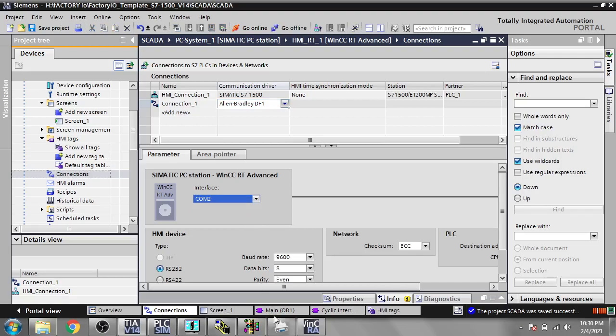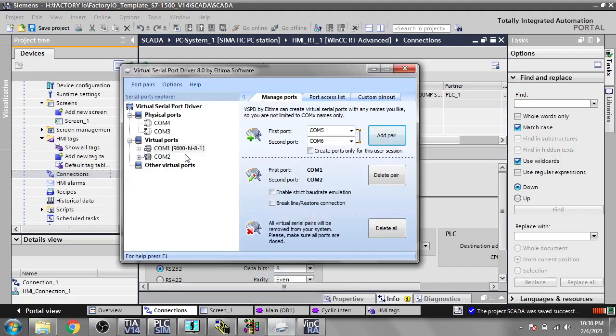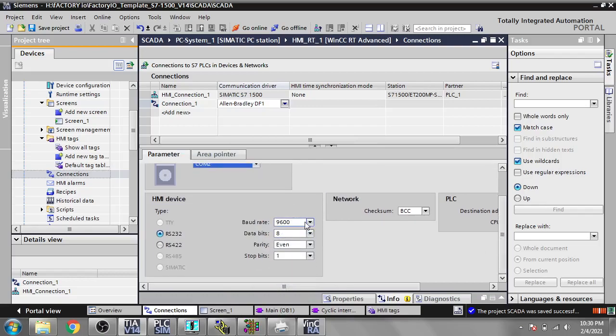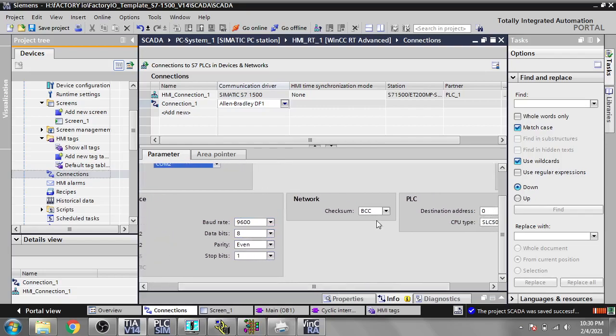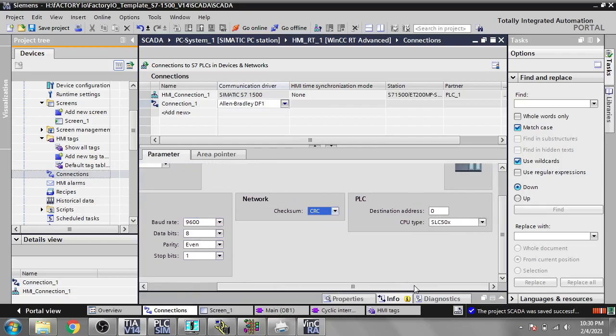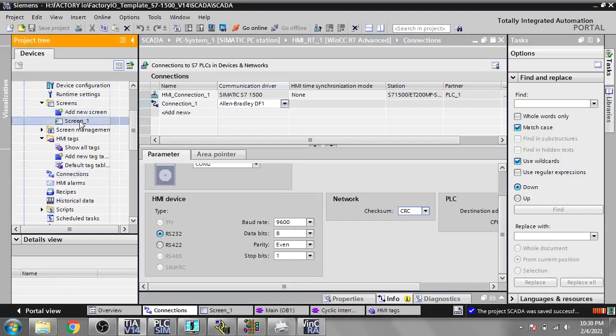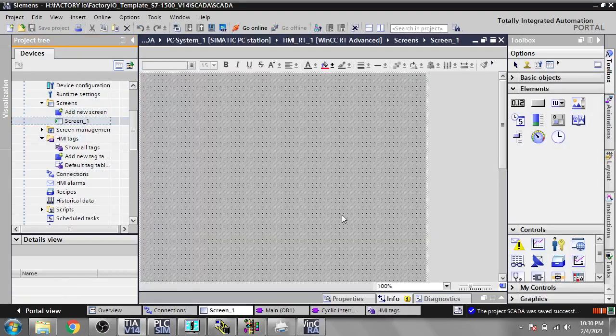For this connection I am going to select COM port 2. We have a pair of COM ports — COM1 and COM2 — so I am selecting COM port 2. The settings are 9600 baud, even parity, 1 stop bit. I am going to change the error check to CRC and the connection will be ready. I will save that.